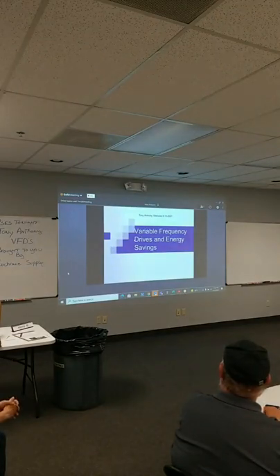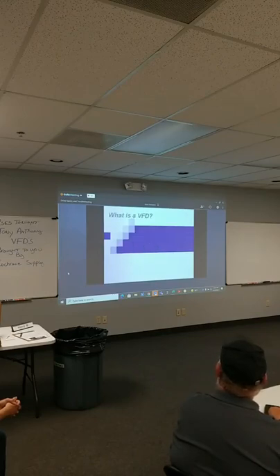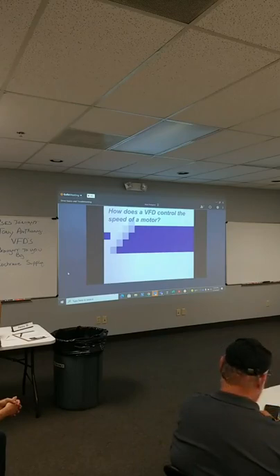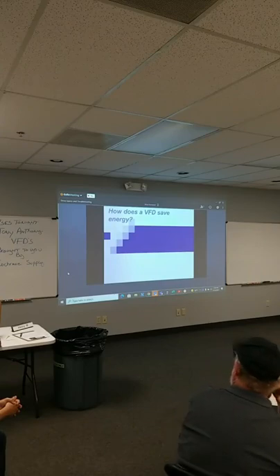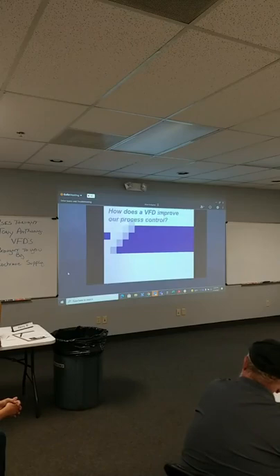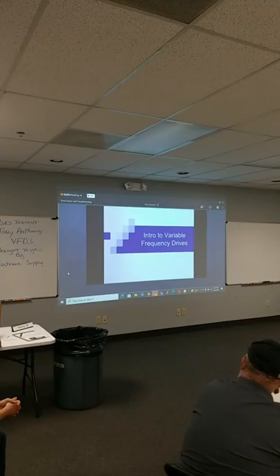All right, so now you can see, we'll get into the basics of a drive and a little bit about what you can do before the drive, how the drive works, and then after the drive to take care of your equipment. So basically we'll cover what a VFD is. We're going to go a little bit more into how it controls the speed of a motor. We're going to talk a good bit about how it saves energy, which is one of the biggest reasons drives exist, especially in the commercial world. Process control, and then we're going to do a little bit of, like I said, intro to variable frequency drives.